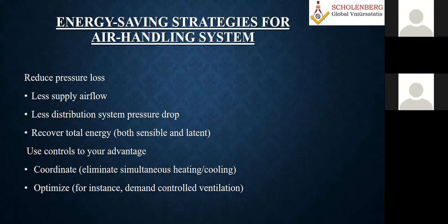So now come to the air handling system. In the air handling system, you have to design from the indoor air quality point of view, but you also have to design from the energy saving point of view. That is where your controls play a very important role. Many times, as I told you, the controls have so much inertia, so you should not compromise by going for low quality controls. You should always go for better quality and a very reputed make, which has good sensitivity and durability.